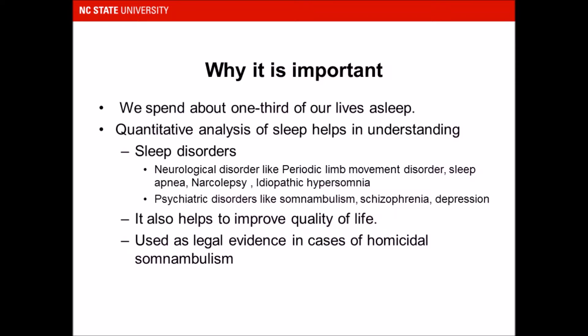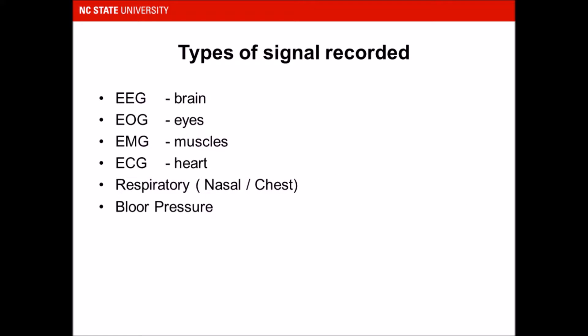Now we will see how polysomnography is done and what types of signals are used. The following signals are recorded in a typical polysomnography: first is EEG, which records brain activity; EOG, which is electrooculogram, which records activity of the eyes — we will shortly see why recording EOG is important; we record EMG to see muscle activity, which can be used to diagnose periodic limb movement disorder; and we record ECG to see how the heart is working and whether there are any abrupt conditions occurring while asleep.